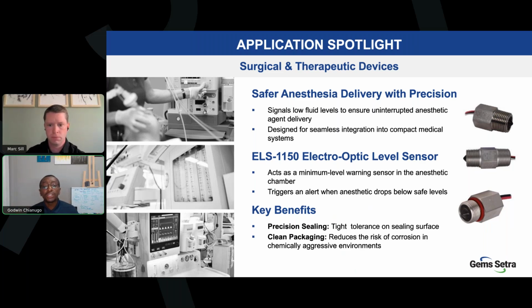What's powerful here is a dual layer of safety. Visual level monitoring can be maintained if it's paired with an electronic alert. This helps meet regulatory safety standards while improving caregiver confidence in uninterrupted anesthetic delivery. If we think about where the GEMSETRA ELS 1150 stands out, we've partnered directly with vaporizer manufacturers to address one of their biggest concerns, seal integrity.